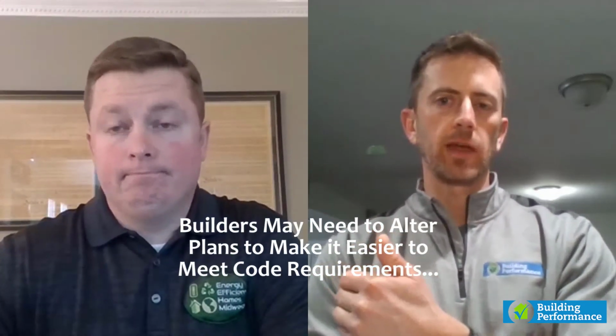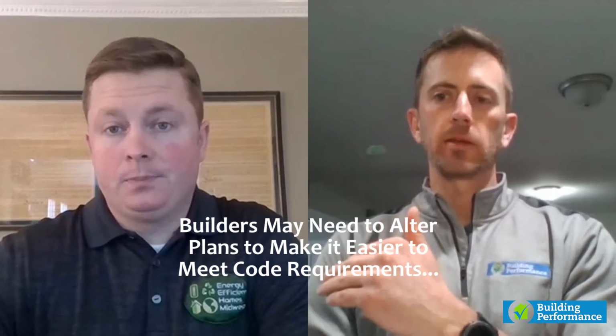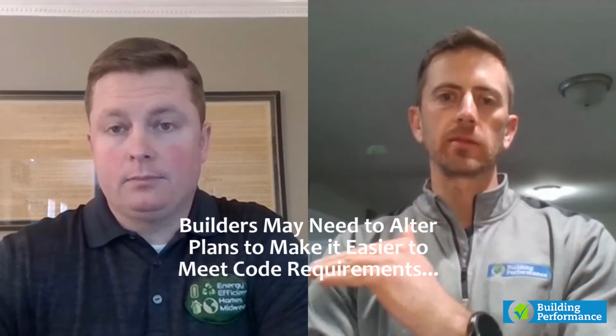So like if you've been building a certain way, say building patio homes that are all 1,500 to 2,000 square feet, and now you're finding it difficult to meet this duct leakage requirement, you might want to think about how you're constructing or insulating the house so that the ductwork is actually inside the conditioned space.